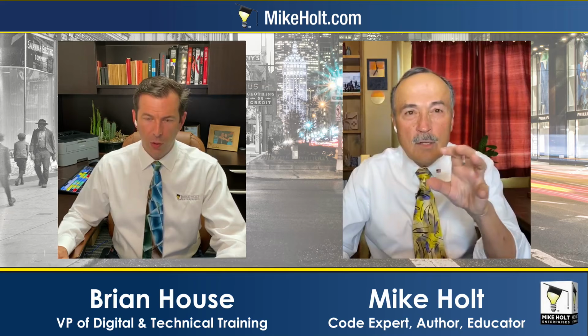Yes, Brian? Just a quick comment from Eric. He says, while a fault probably wouldn't melt the fuse, depending on the voltage, they use relays for many other reasons, so that the ground fault can actuate devices and set settings. So it looks like with resistance grounding, they're using it also to actuate different types of relays and probably initiate disconnection and safety sequences.